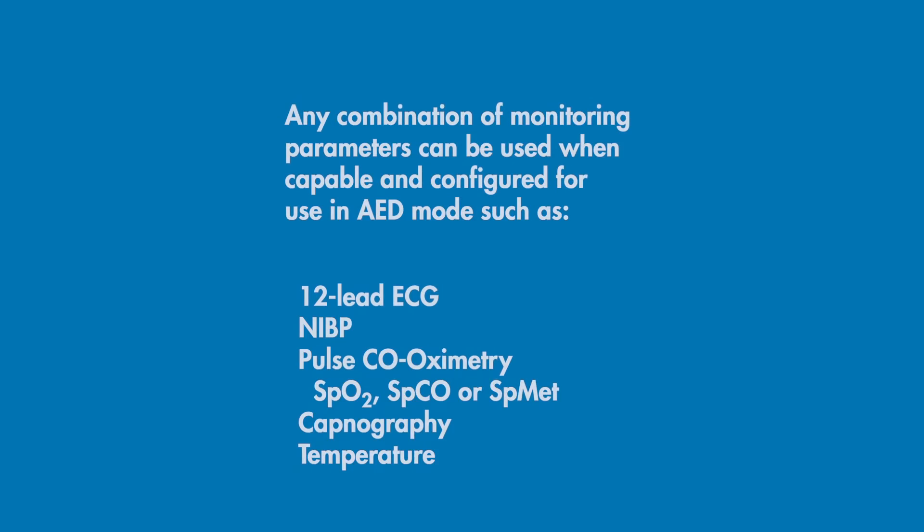Any combination of monitoring parameters such as 12-lead ECG, non-invasive blood pressure, pulse co-oximetry including SpO2, SpCO or carboxyhemoglobin, SpMet or methemoglobin, waveform capnography, or temperature can be used when capable and when configured for use in AED mode.